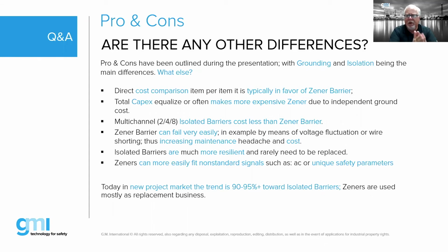Historically, one of the advantages of Zener barriers was a very small footprint, meaning that they were very thin. So your density of Zener barriers in a panel, you could shrink your panel down based upon the amount of Zener barriers. What you are finding nowadays, however, is that GMI, with their latest range of galvanically isolated barriers, the latest generation, are much thinner. They're actually taller and wider, but thinner, meaning that from a stacking density standpoint, being able to put a significant amount of barriers on a single piece of DIN rail, you now can do the same types of things with galvanically isolated products that previously took up an awful lot of space. So that's one advantage that is now there.